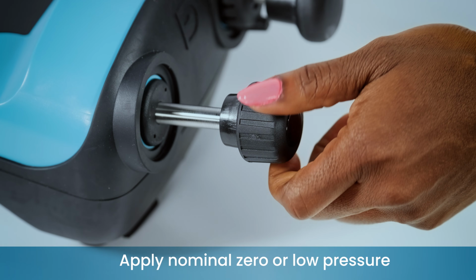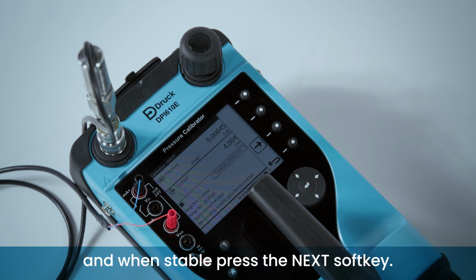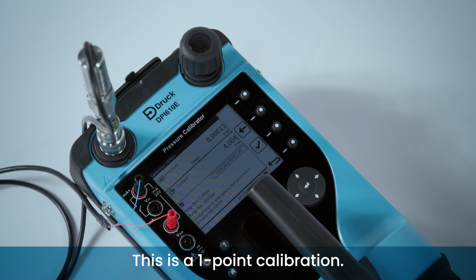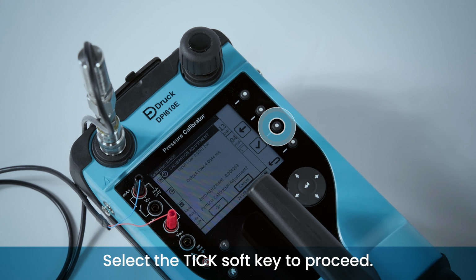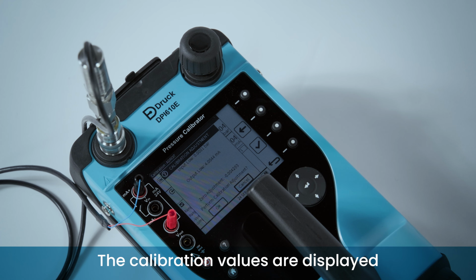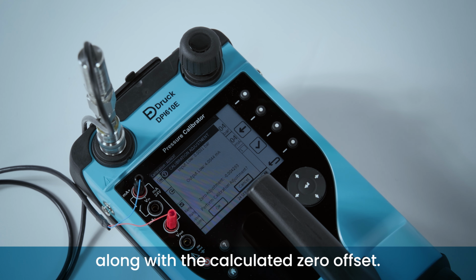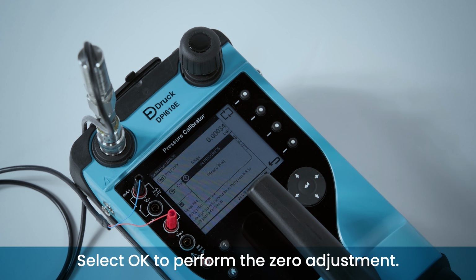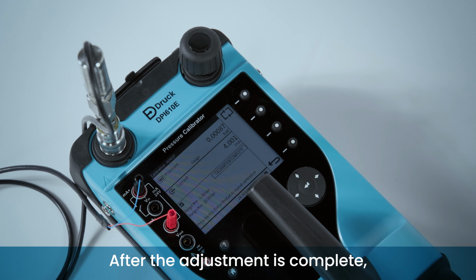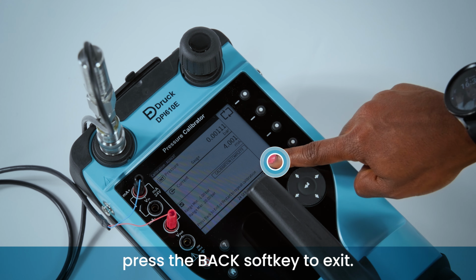Apply nominal zero or low pressure, and when stable, press the next soft key. This is a one-point calibration. Select the tick soft key to proceed. The calibration values are displayed along with the calculated zero offset. Select OK to perform the zero adjustment. After the adjustment is complete, press the back soft key to exit.